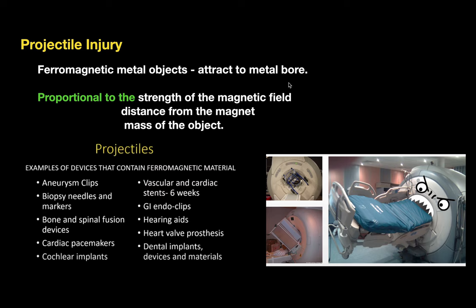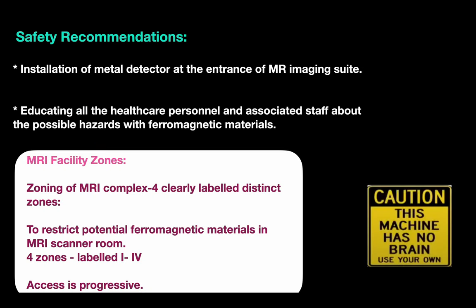Regarding projectile injury, ferromagnetic metal objects can be attracted toward the magnet bore. The risk depends on the strength of the magnetic field, distance from the magnet, and mass of the object. Potential projectiles include aneurysmal clips, biopsy needles and markers, bone and spinal fusion devices, cardiac pacemakers, cochlear implants, vascular and cardiac stents implanted within six weeks, GI endoclips, hearing aids, heart valve prostheses, and dental implants.